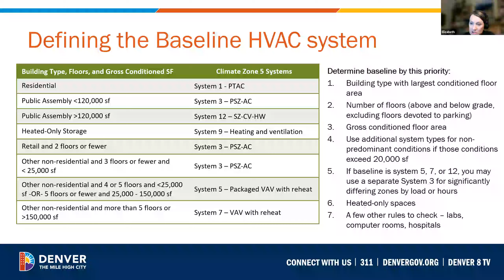Let's look at an example of a project with multiple baselines. Here is a fairly large-ish multifamily project. How would we go about selecting our baseline or baselines? The first baseline is easy. It's residential. So that's a system 1, hot water PTAC. Then we can pull out a second baseline for our non-residential space because it exceeds 20,000 square feet. Based on its size and number of floors, this would be a system 5, which is a packaged VAV with hot water heating and reheat.